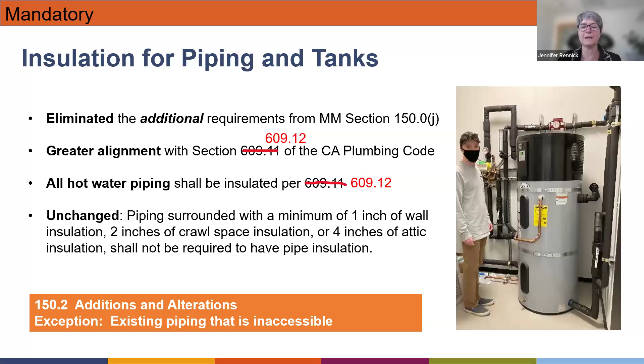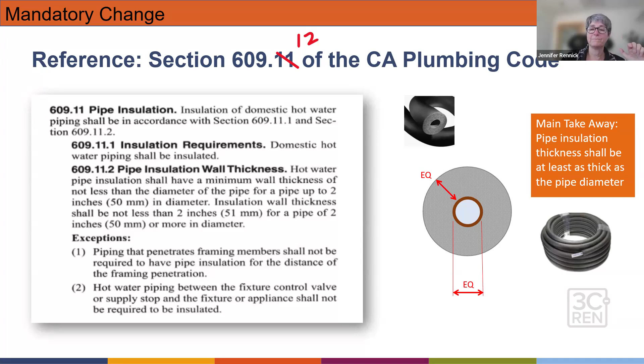And under the new code, it's going to be referencing 12. And the main takeaway is that the thickness of the insulation needs to be as thick as the pipe diameter. And that's for the residential part of the code. They don't explicitly give you an R value anymore. They just do it by thickness. And the thicker, more dense, the better. The pool noodle stuff, a lot of times it's not even the right thickness, but I do see it at the hardware stores a lot and see it on the job sites. Not quite what you're supposed to do. So that's room for improvement.